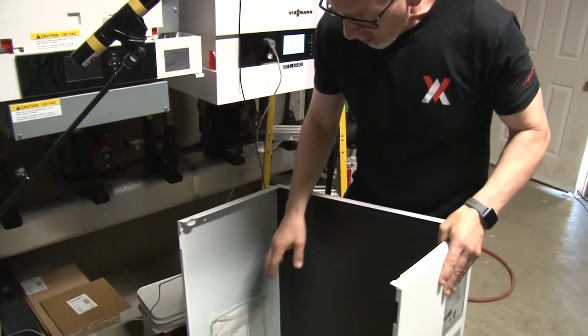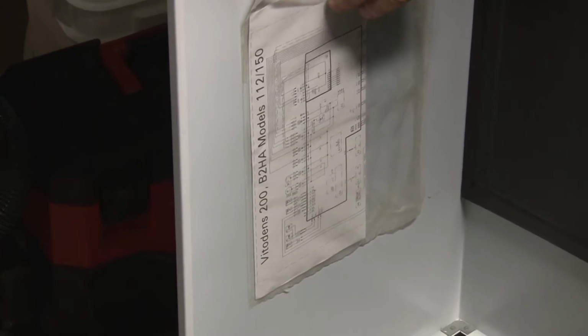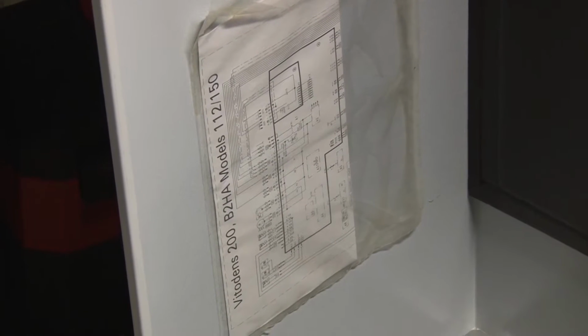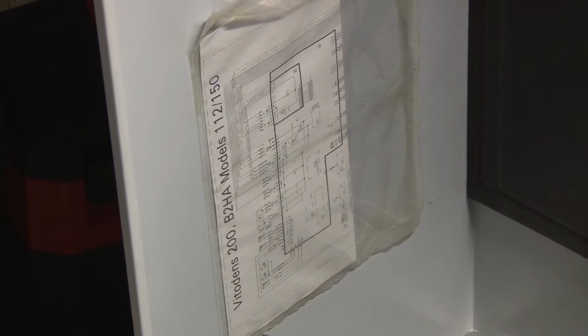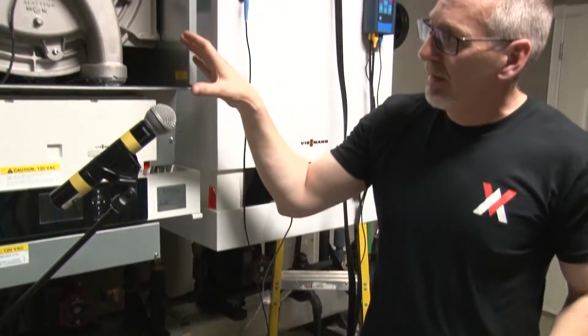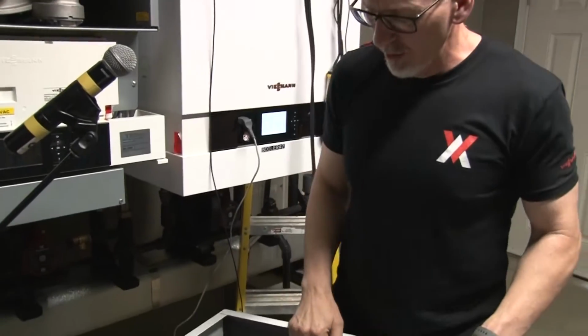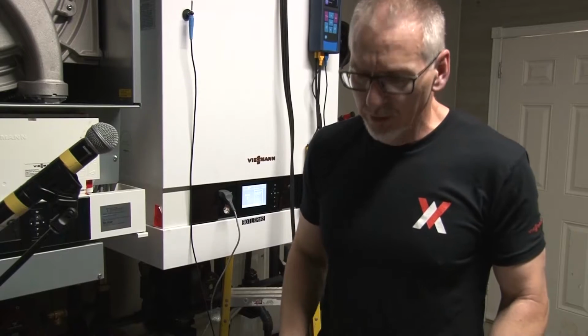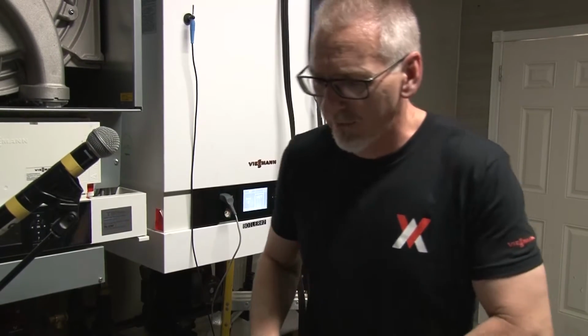Also, I like to point out that on the documentation, a lot of times you might not see the manual I showed you, but you'll have this document. And this is a wiring schematic. It's a factory wiring diagram for the boiler, the internal as well as the external wiring. So I'm pulling plugs off of the boiler here when I'm doing the service, and all those plugs typically have a number on them. This little reference will tell you, once I've got this spare plug, what do I do with this plug? It's got a number on it. You can always refer back to this little schematic and find out where that missing plug is supposed to go. Some guys like to take pictures, that's fine, but there is always this little document that's usually kept inside the boiler. It never disappears from there, and that's a really good area for it. So I just wanted to point that out before we get started.